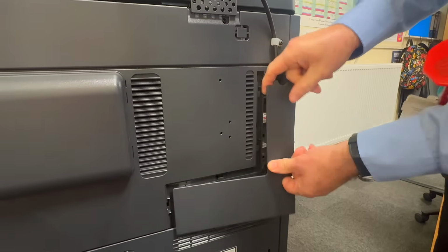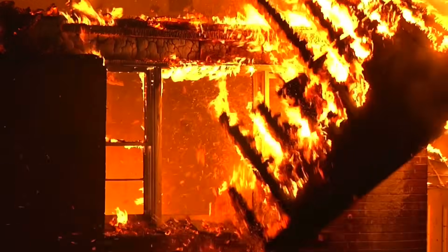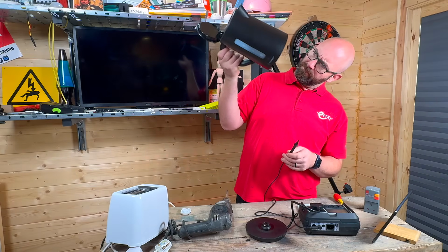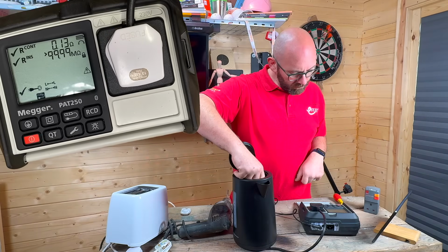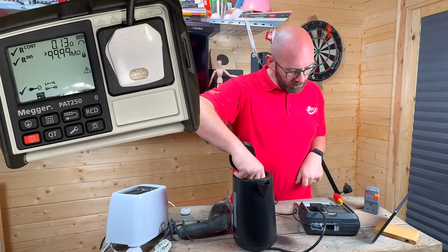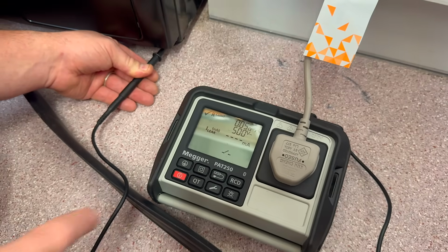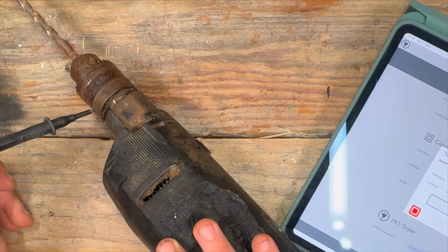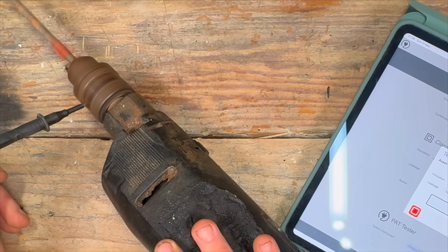You are testing equipment that can shock people, start fires, and take a whole section of a building out if you get it wrong. So in this video, we're stripping it right back and doing the full process properly. User checks, formal visual inspection, and then the combined electrical test using the Megger PAT250. We will walk through continuity limits, insulation resistance, leakage testing, and how those tests change for each equipment class.